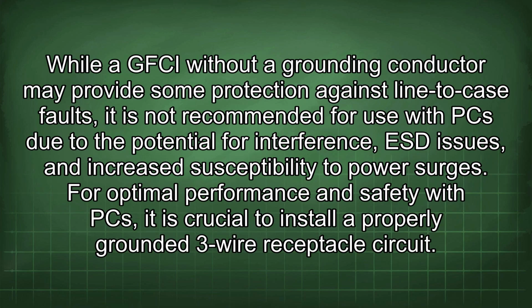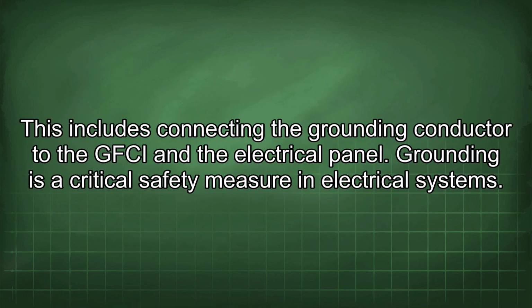While a GFCI without a grounding conductor may provide some protection against line-to-case faults, it is not recommended for use with PCs due to the potential for interference, ESD issues, and increased susceptibility to power surges. For optimal performance and safety with PCs, it is crucial to install a properly grounded 3-wire receptacle circuit. This includes connecting the grounding conductor to the GFCI and the electrical panel.